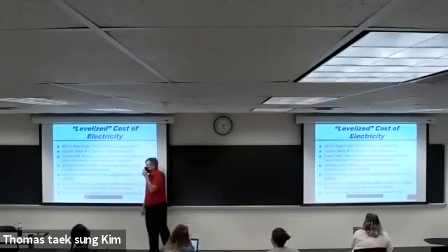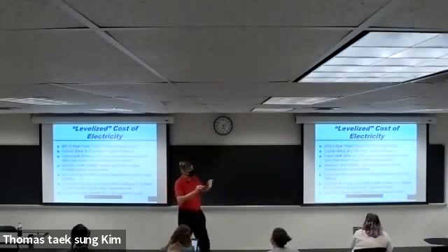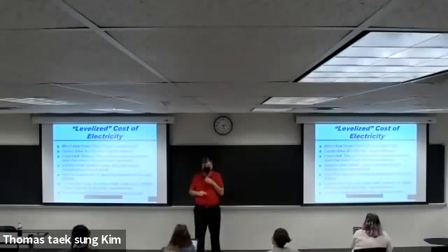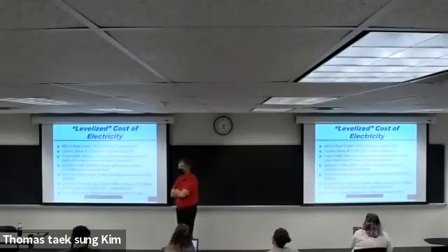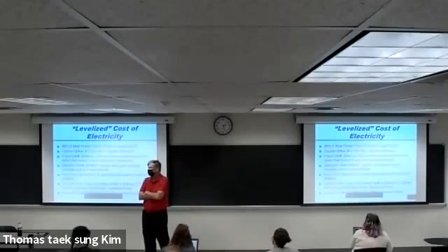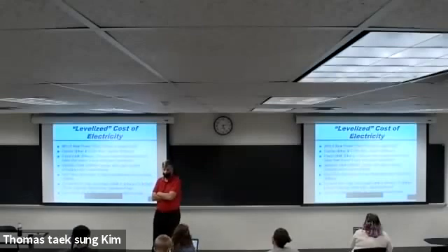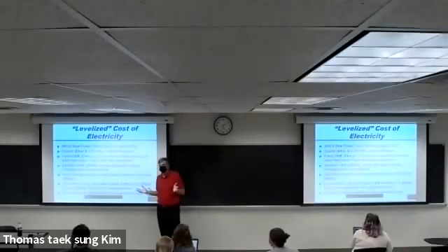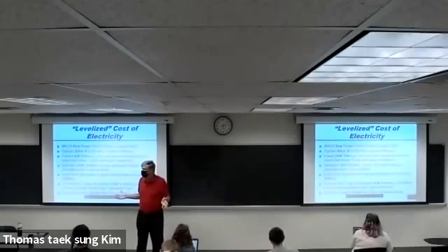That's stated in dollars per megawatt hour, variable O&M. But if you have a scrubber, typically there's a certain amount of reagent that's used in the scrubber to basically react with sulfur dioxide, often lime or limestone, and it removes sulfur dioxide from the air. So it takes out, at most coal plants, 95% of the SO2. Takes out a lot. It's very effective.